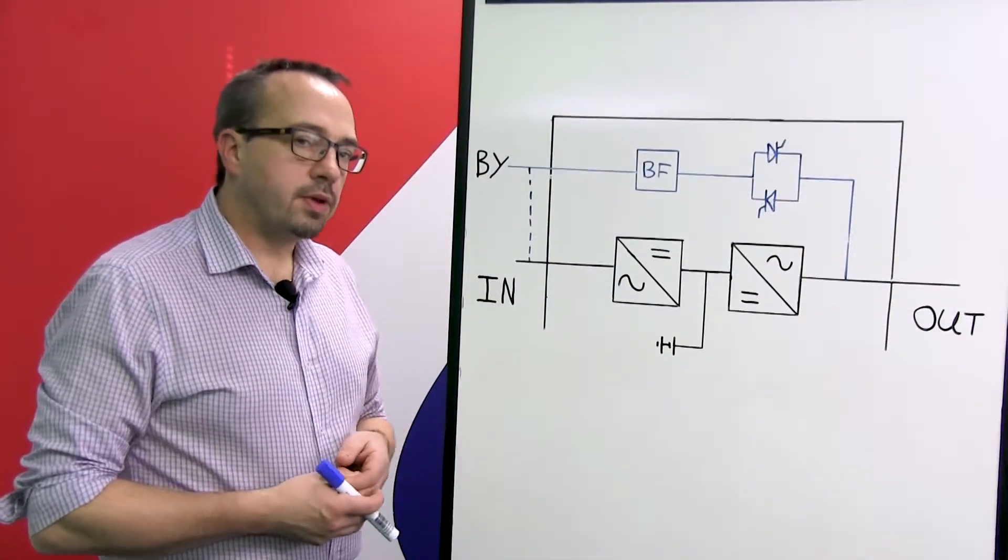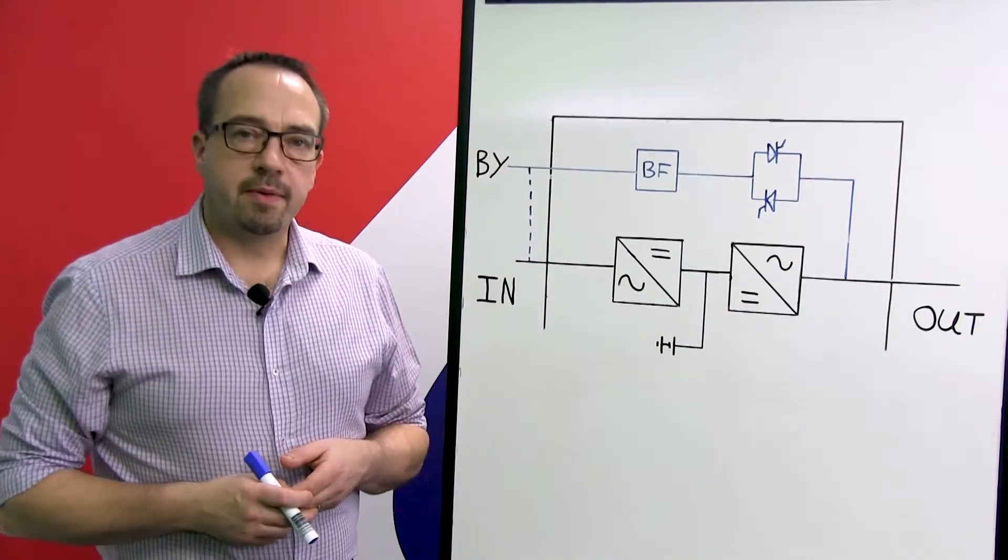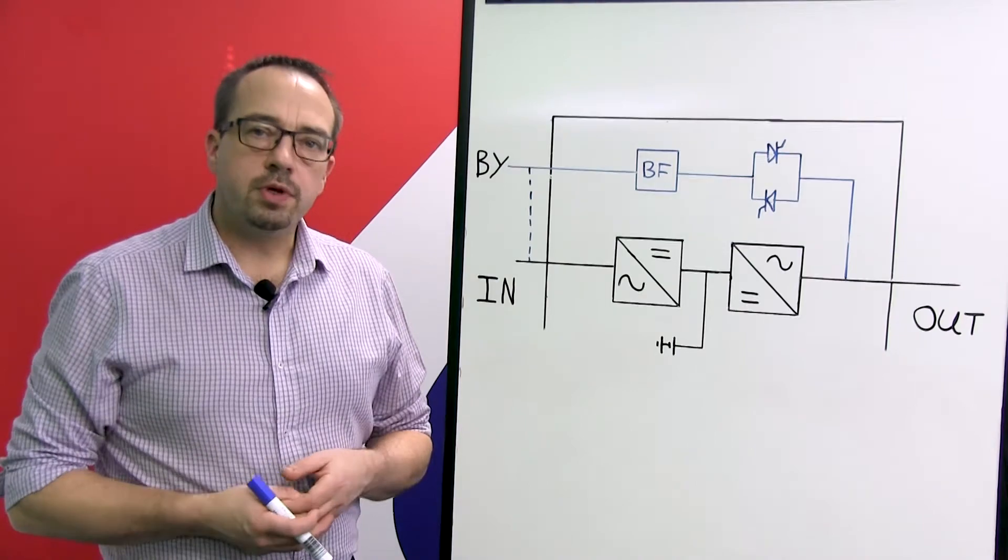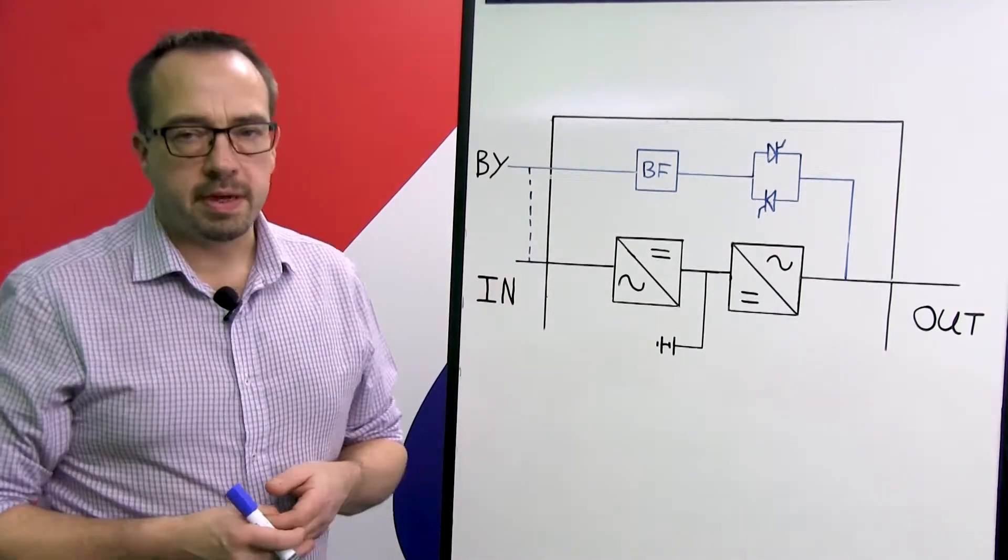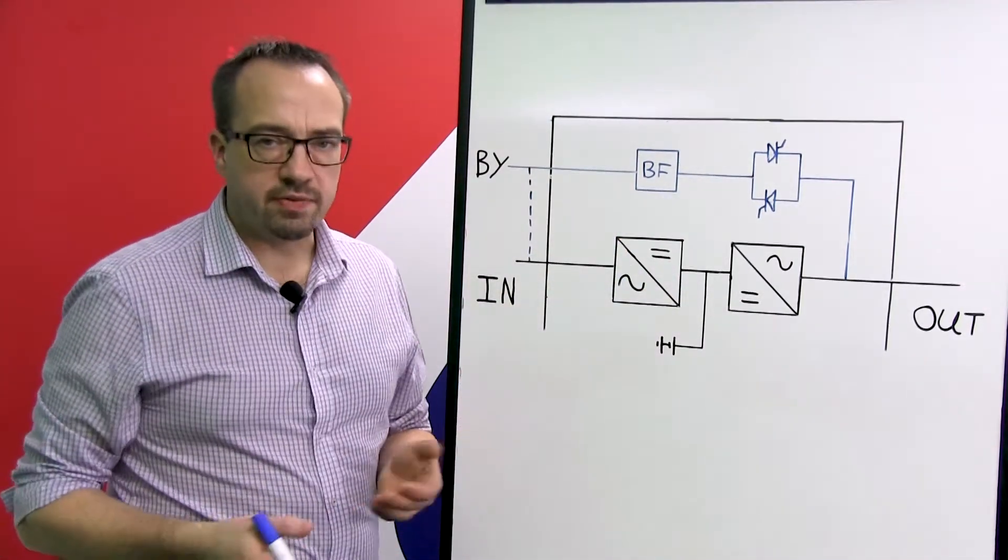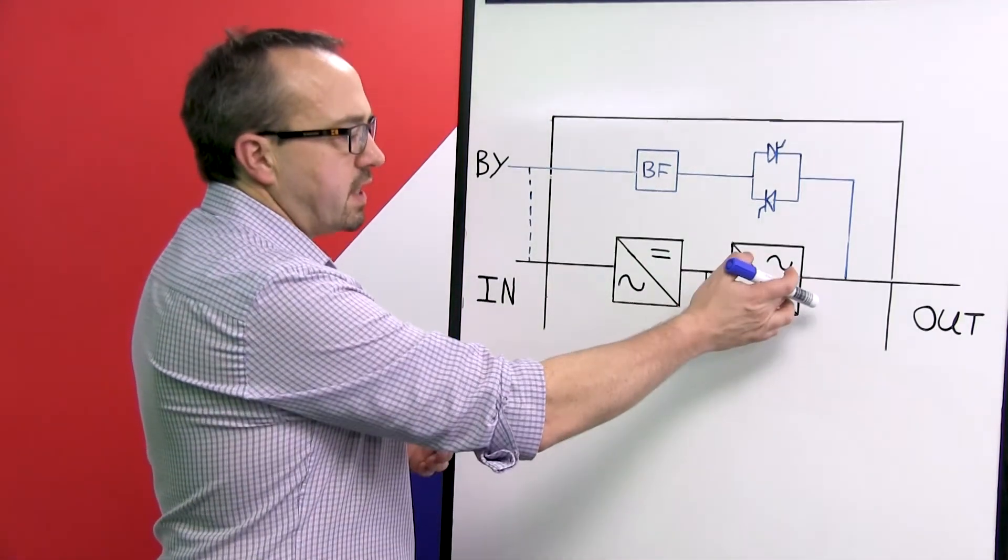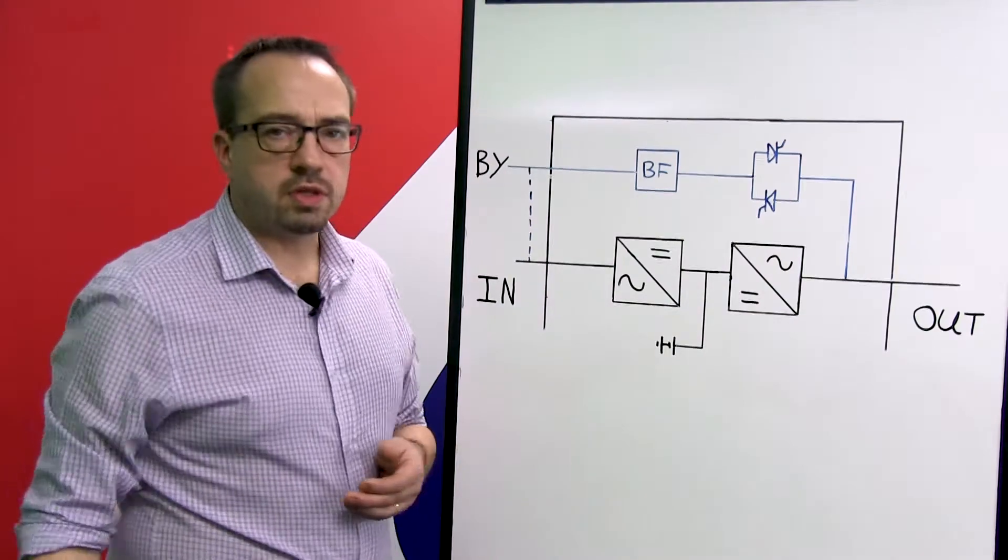If we take a look at the diagram on the board here, this effectively is a basic block diagram of an online dual conversion UPS system. The online dual conversion UPS system operates by taking the voltage from the incoming main supply, converting that voltage from AC to DC via the rectifier, then we re-invert that voltage back from DC back to AC again by the inverter in order to supply that voltage to the critical load.